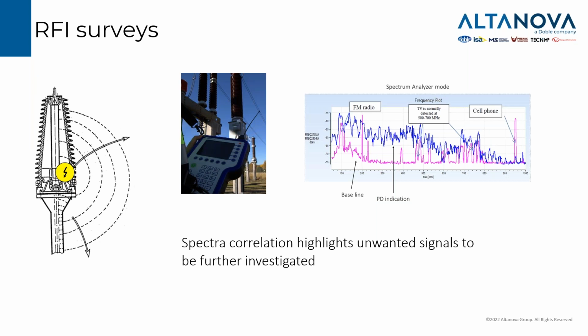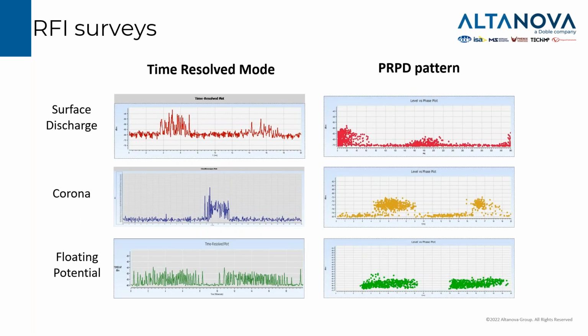You can see here a few pictures about defect propagation, signal propagation outside of the cable termination. We can pick it up with a UHF antenna, and on the chart on the right you can see the spectrum of background noise in purple and with signal in blue. By studying such a spectrum, we can get some information, first, let's say, level information, if we have an unexpected signal in the asset we are testing. We have here some information about which kind of defect we can find with respect to their spectrum frequency and the related phase resolved PD pattern.